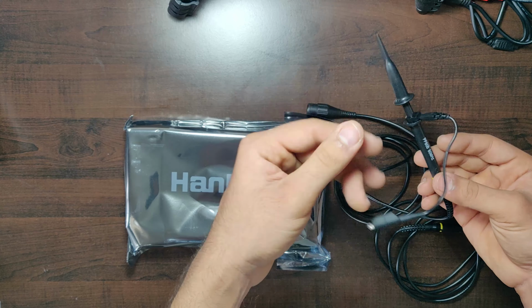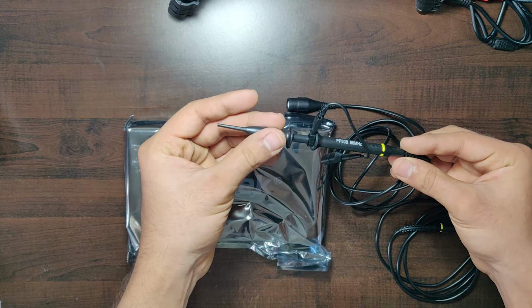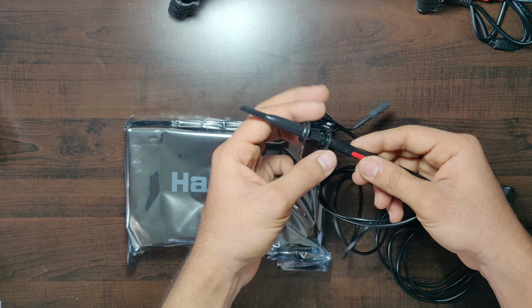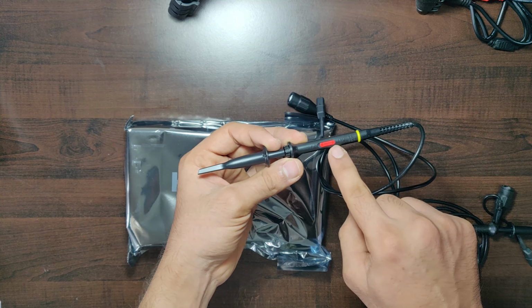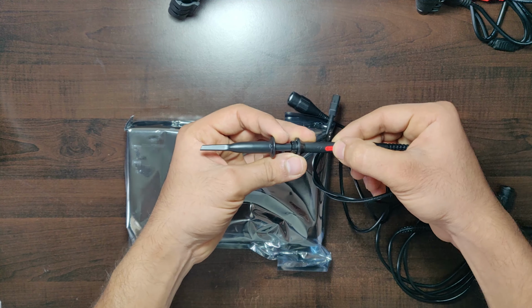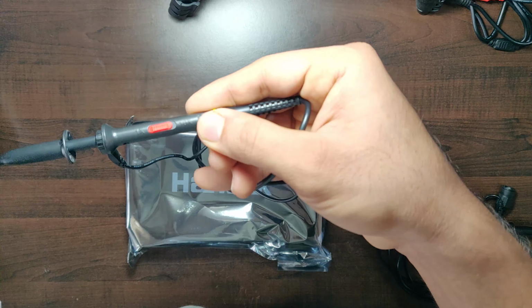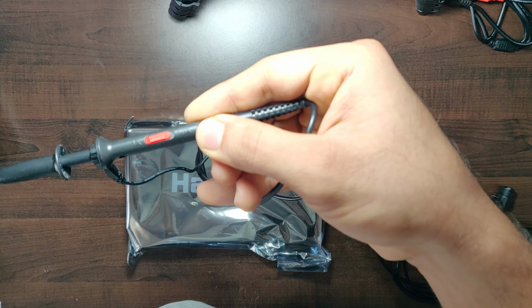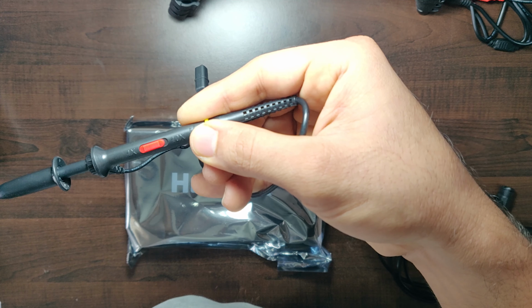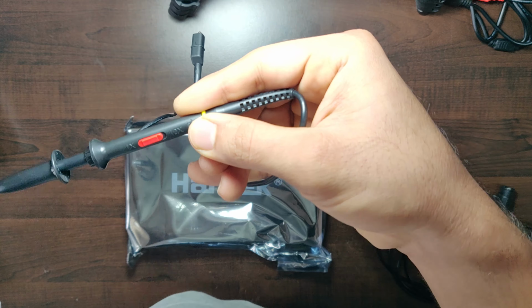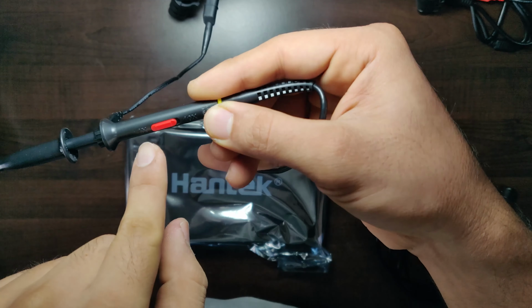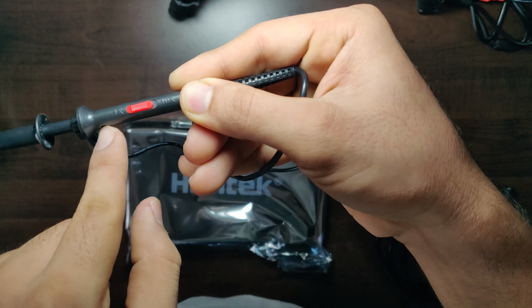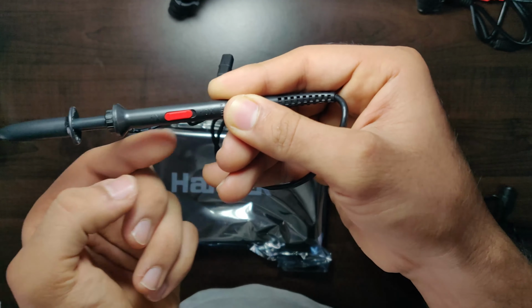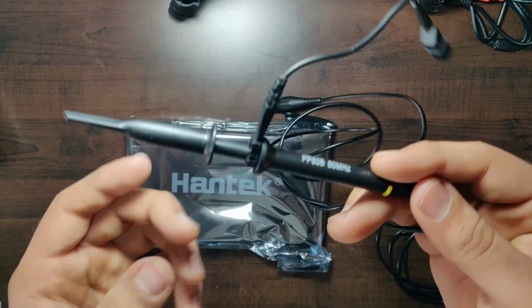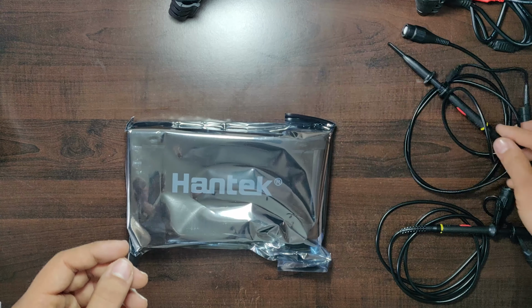So here you can see on the left side of the cable which I was holding is a ground cable which you connect to the ground, and the top one, the other port, is the hook that is also called as a hook tip. And here you can see a slide switch which is actually very important for the attenuation, set the attenuation ratio, that is 1x and 10x. You have two options, and this has a bandwidth. The probe has a bandwidth of somewhere around 80 megahertz.